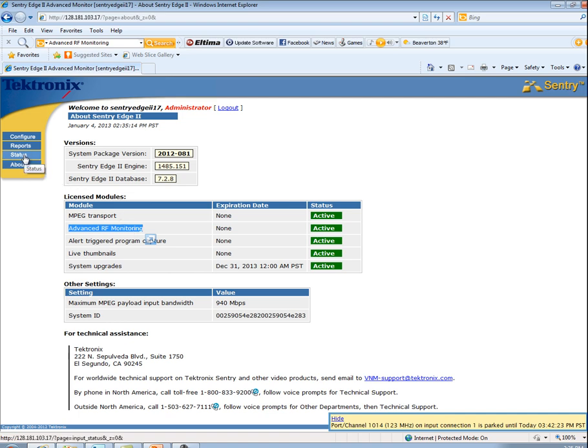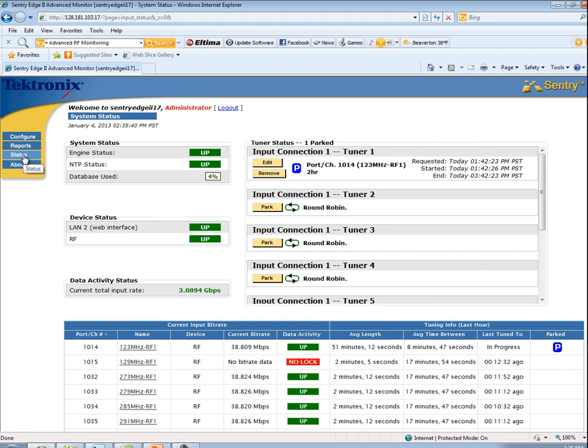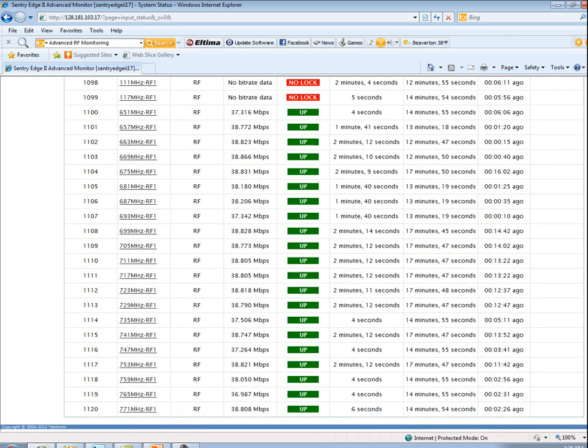So the next page I'll look at is the status of the RF tuners and what they found. And based on a previous configuration, which I'll go through at the end, we have a wide variety of RF channels being delivered to my desk over QAM. We can see in the lower left-hand corner each of the channel frequencies or names that we've assigned to them, starting at channel 14. And the reason I don't have 2 through 13 in there is because this local provider has analog NTSC, so I'm starting at the first digital one that we have. And then if I scroll all the way to the bottom with the browser, we can also see that we're making it not quite up to the 850 range, but most of the 850 megahertz is being used by this product or this cable provider.